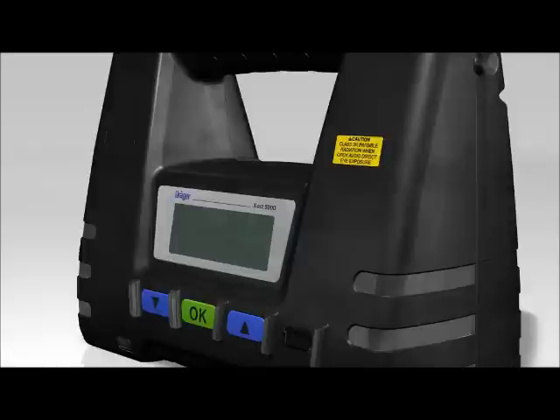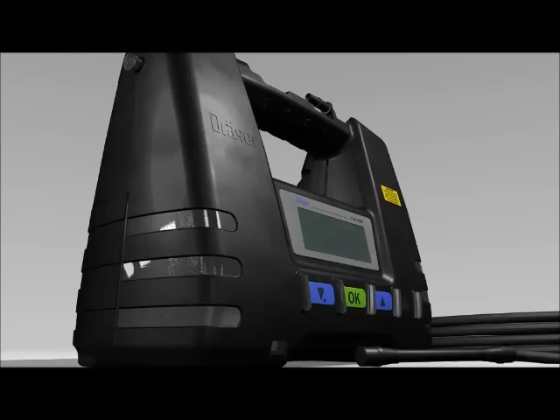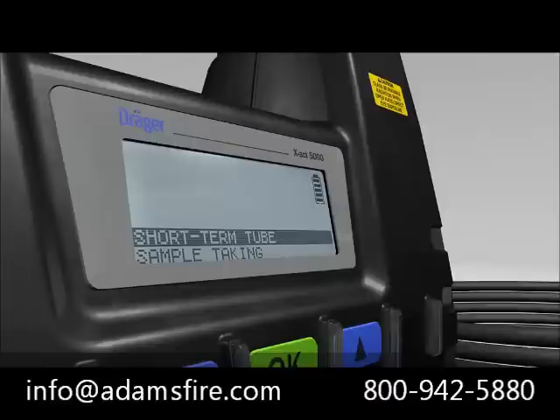The Dräger X-act 5000 features a robust ergonomic design and is suitable for use in explosive gas atmospheres. For measurements in inaccessible areas, the tube pump can be used with extension hoses up to 30 meters in length. The three-button system can even be easily operated when wearing protective gloves, and the menu structure is simple and intuitive.